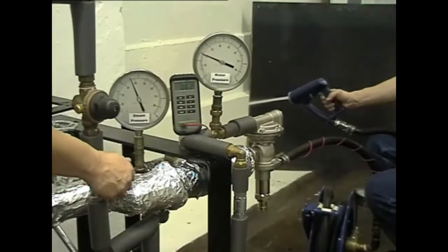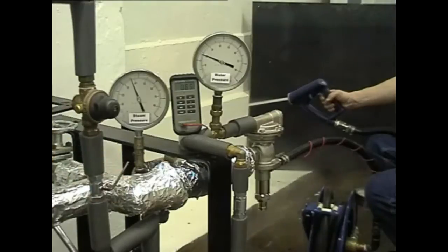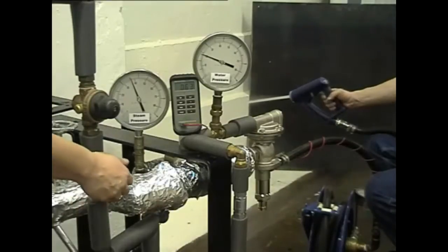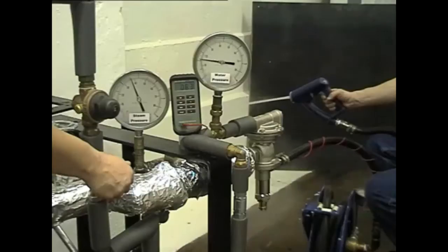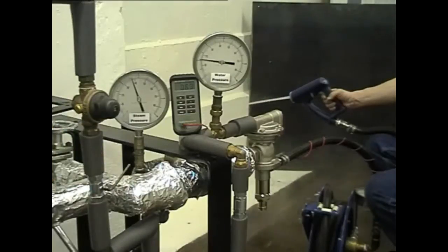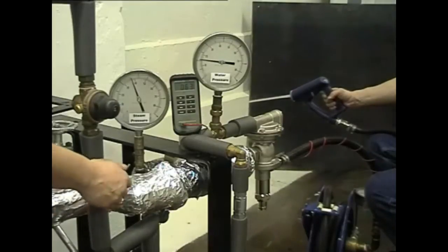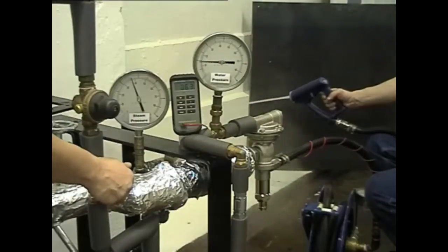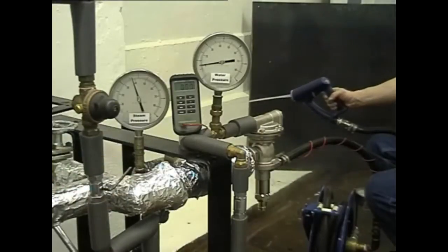20 psi. 15 psi. And finally 10 psi, the SWM1 continues to maintain constant control of the hot water temperature.